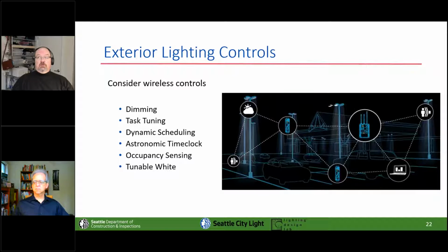So we don't necessarily have to always pick one light level. This can be useful for dimming for changing light levels over time, making use of adaptive compensation. As the night goes on, we can ramp the light level down as our eyes need less light. It also means we can task tune our parking lots. If we're looking for 3, 4, 5 foot candles in a parking lot and we're getting 6, 7, 8 foot candles, we can task tune that down, which gives us remarkable savings.